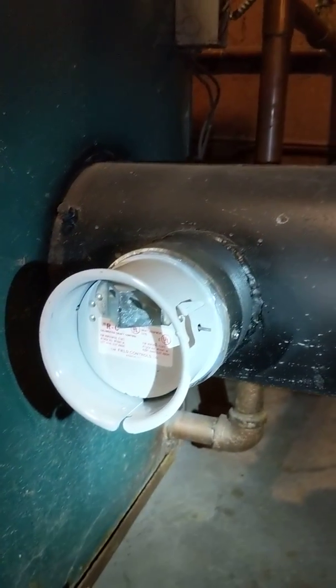We've got our exhaust motor over here — 308 stainless. New install is the barometric relief pressure. I had issues last year with excessive winds forcing air back into my hopper and having hopper fires.